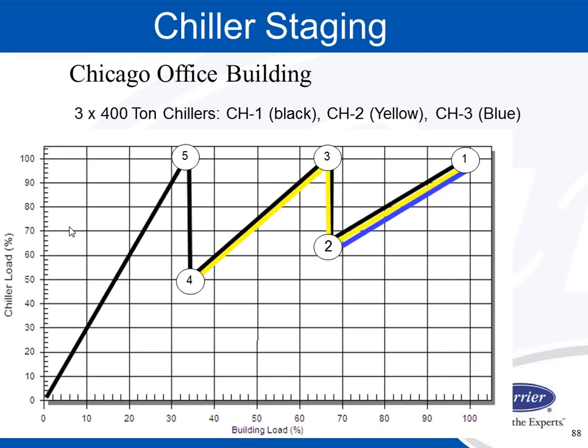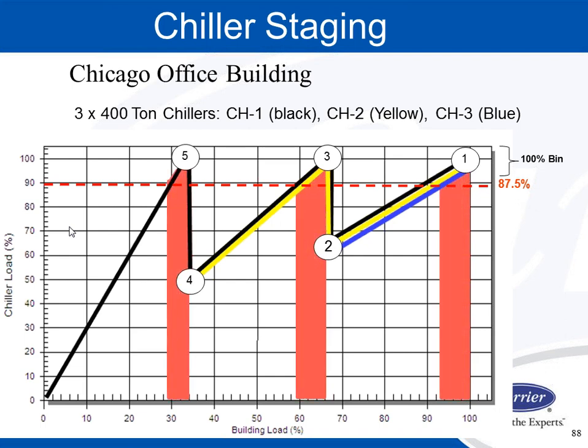So let's look at the bin data from an IPLV standpoint. The 100% load point is from 100 to 87.5%. That means points 1, 3, and 5 would be in that 100% load point, and that shows a representation of the line shaded in red. That is what the 100% load point bin looks like.